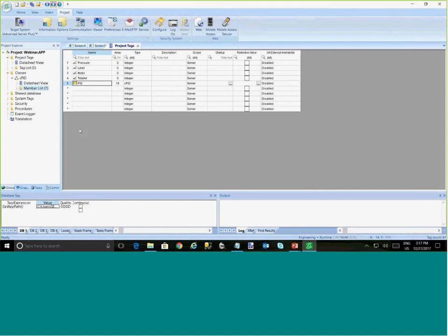Several advantages. First, time to create the tags. It's much faster to do what I did here once than creating all those 77 tags manually. Second, during the runtime, you can use indirect tags and a tag as the index of the array or linked symbols with the class tag to minimize work when designing screens and writing scripts as well.